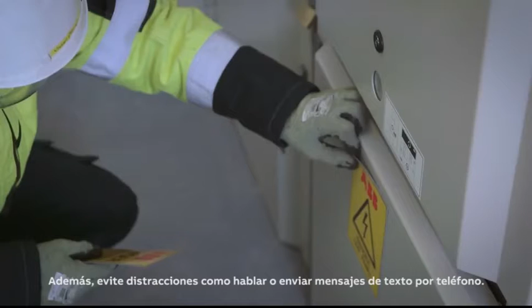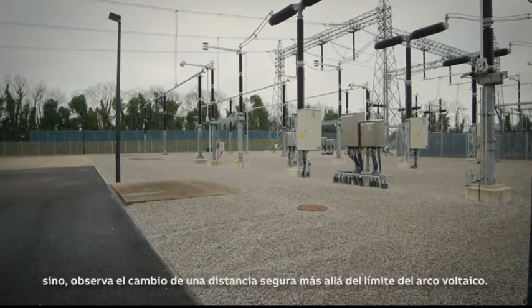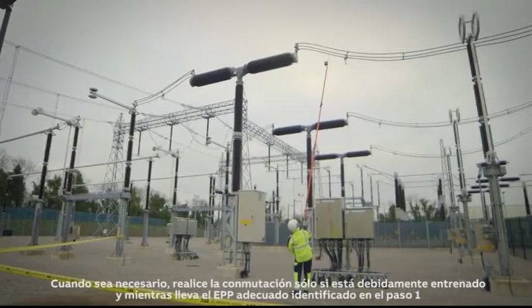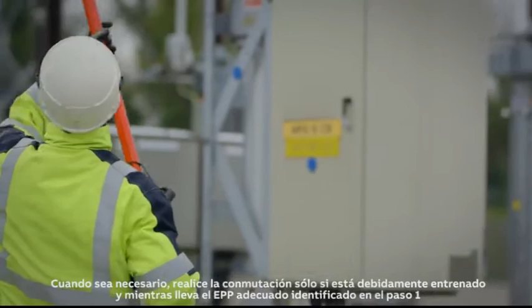Step 3A. Disconnect all sources of supply. Where possible, ABB recommend that switching should be conducted remotely. If not, observe switching from a safe distance well beyond the ARC Flash boundary. If switching is performed prior to arrival, walk down the equipment to check the isolation points upon arrival. When required, perform switching only if properly trained and while wearing the proper PPE identified in Step 1.